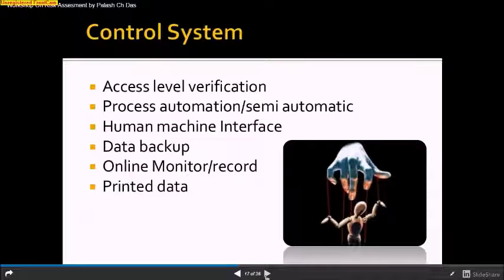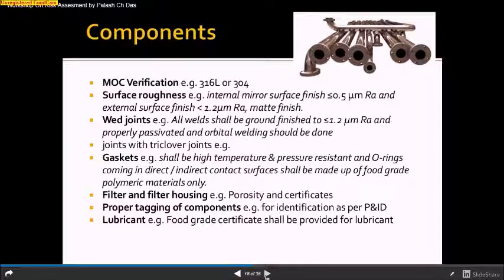Next is a very critical part, that is components. As you know, in a medicine manufacturing facility, we are always talking about product contact parts. Suppose there is a vessel where you are going to mix a solution, any surfaces. So MOC verification is required, and you need to mention exactly what MOC you want. Surface roughness is also a critical factor. You need to check whether you want an internal mirror surface finish or external. For internal and external there is a different Ra value. This is called the roughness factor. Again, weld joints: how they are joining the weld, and whether the welder certificate is available or not. These are the critical things. Gaskets: whether your gasket can withstand high temperature and pressure, where you are planning to put a gasket in the PHE or MCDP, where the temperature is more than 100 or 80.